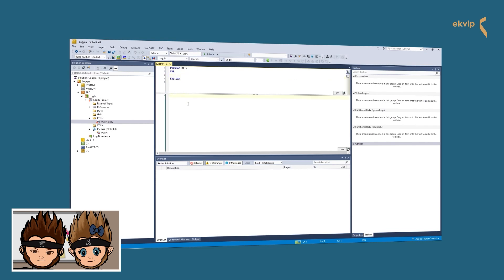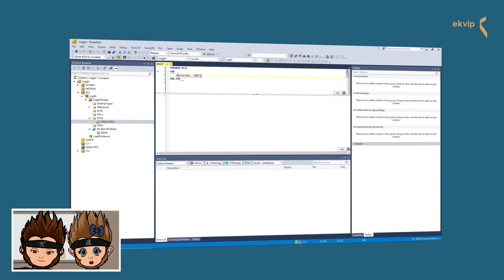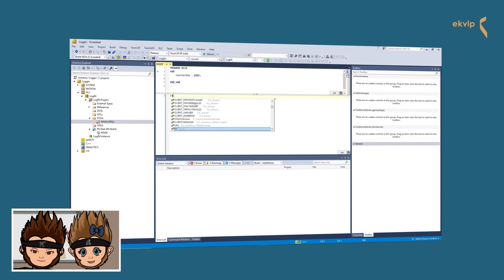As said before, we will work with a simple example, so we just declare one variable. We write its name between VAR and END_VAR — let's name it counter1, because it will be a counter. Behind the variable we indicate the type and end the line with a semicolon. As type we choose DINT — DINT stands for double integer. We will also explain more about variables and their types in a further video.